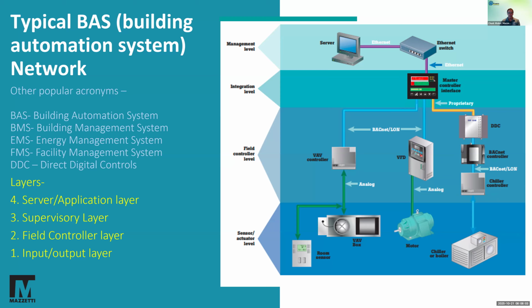So the basic layout of a DDC system is you have your sensor or actuator level. This is where the equipment lives, down at the first level. Second is the field level controllers, where you have the controllers interacting with all of this. You have an integration level where it's all pulled into a master controller, and it gives you the readouts and sometimes the graphics.